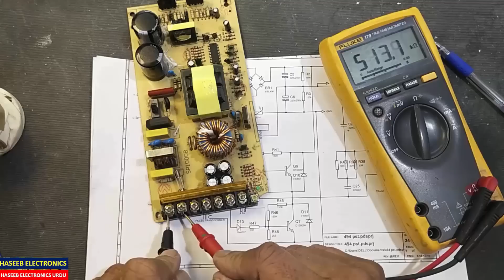Then the next thing, set the multimeter to ohm. It is the cold testing. Check the input resistance across both terminals. It is 515K and it is increasing. That's good. If it is less than 50K, say 10K, 2K, or less than that, that means the power supply has damage. So if it is increasing above 500K, that means the circuit is safe. It is the first indication for the circuit. If we cannot find the resistance, then we need to check this fuse and the next circuit.